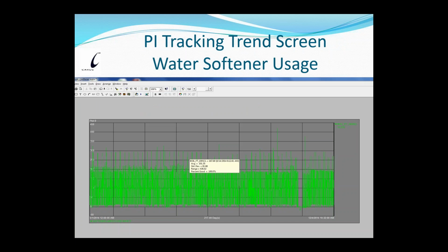Matter of fact, this one is right here. This is 217 days of gallons per minute water flow exiting the water softener. The little part here shows that the average is 101.35 gallons per minute for that entire time period, even when we had this one downtime right here. The reason it looks like it's going up and down so much is the water softener flow rate changes based on our RO storage tank level. As the RO storage tank level drops, the trains then kick on and they accept water from the water softener. When we reach the desired level in the RO storage tanks, then the train pumps shut off and the flow drops down to nothing, basically. So it's a constant cycle of up, down, up, down. When we are pumping, we're pumping about 220 gallons a minute through the water softeners to the RO system.